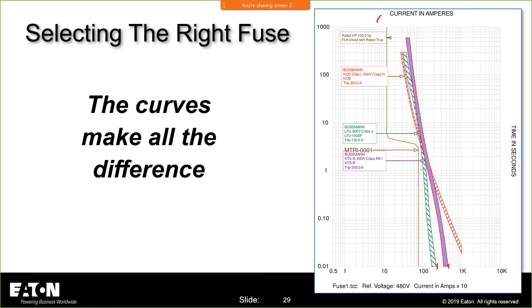Once you get upstream in the power distribution system, your inrush currents aren't going to be as large. If you think about a one-line diagram, if you have a motor down here and you have a bunch of motors with fuses on these motors, and then they add up and you come up to another bus, and then you have another fuse up here. This fuse, because these motors are turning on and off at different times and not all coming on at the same time, is not going to see as drastic an inrush as you would expect when you're down close to the load.